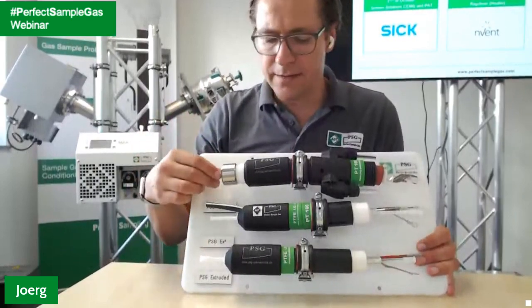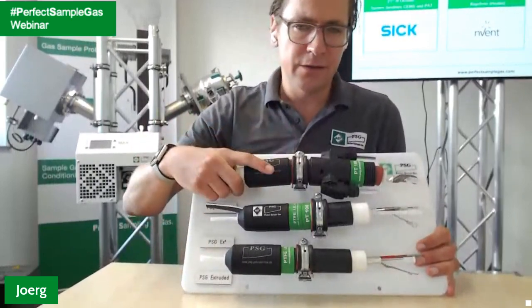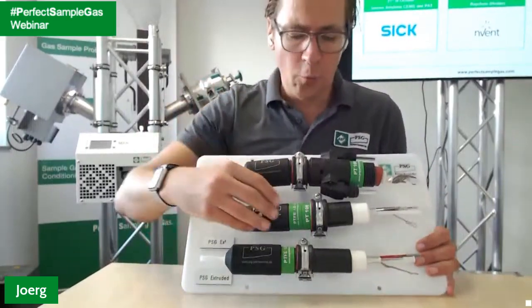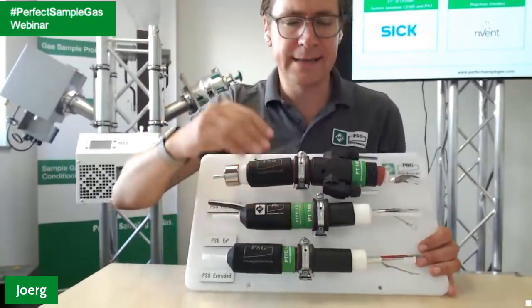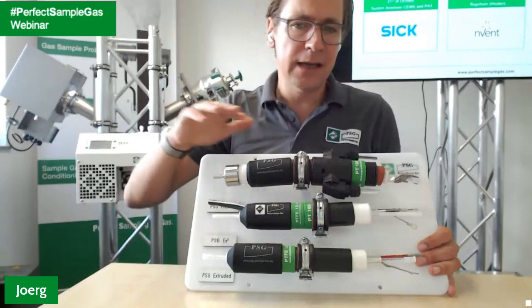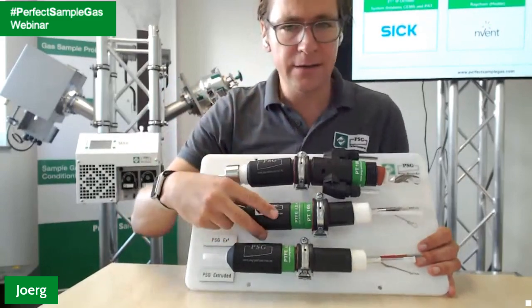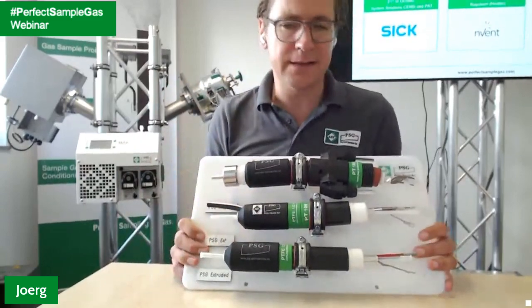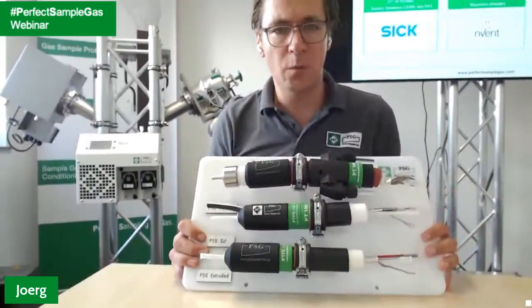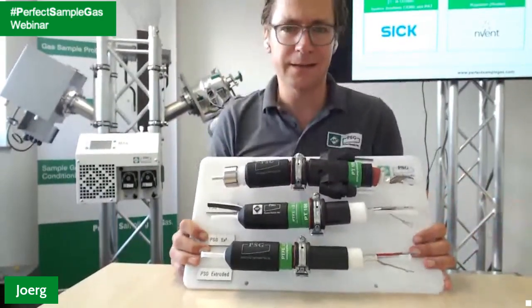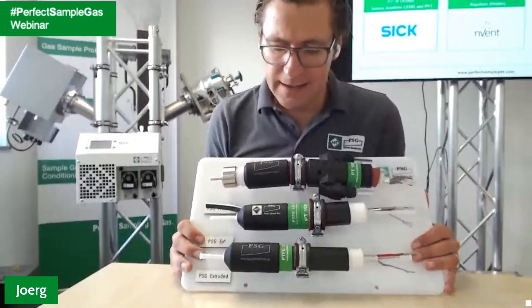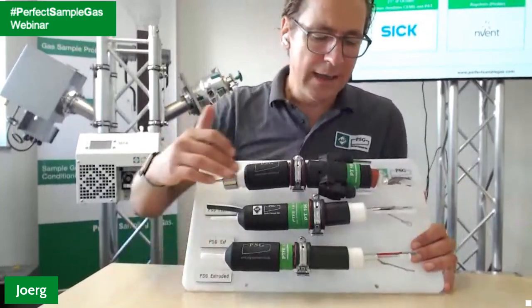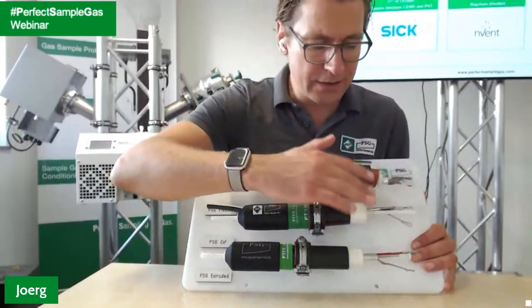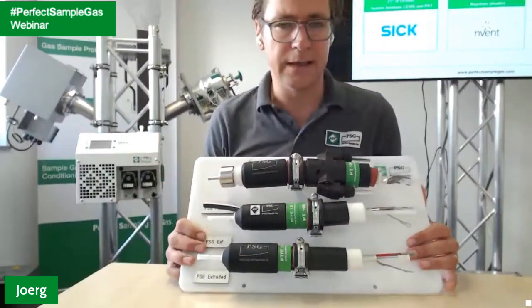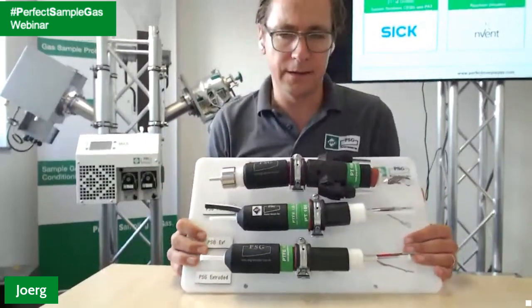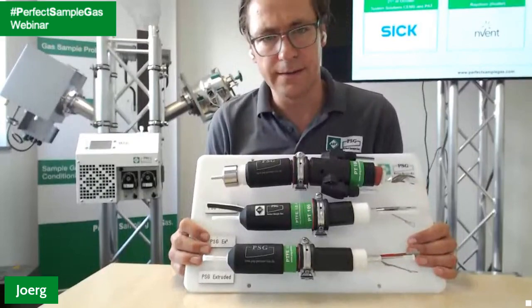Therefore it's important that you have a heater which supplies the same heat in every area of your line. Doesn't matter if it's 10 meters, 5 meters, 100, 150 meters, you have to make sure this is heated properly. The insulation material and the design of the heated sample line are very important.